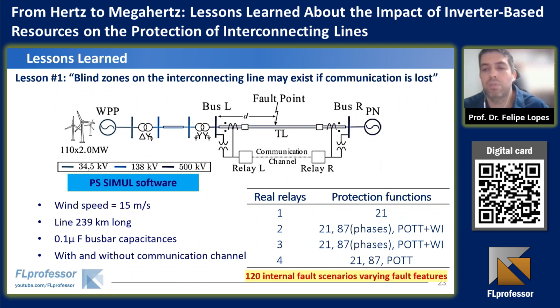And we could see here that the differential and pilot schemes operated with very good performance, but the distance element was very affected, especially at bus L, the local bus where the IBR was connected. And in this sense, we prepared a figure to demonstrate how much coverage we could have in each case, with the communication channel available and without it. And at that time, we could conclude that there is a blind zone close to the IBR in which the protections can simply not operate even if the fault is inside the system.